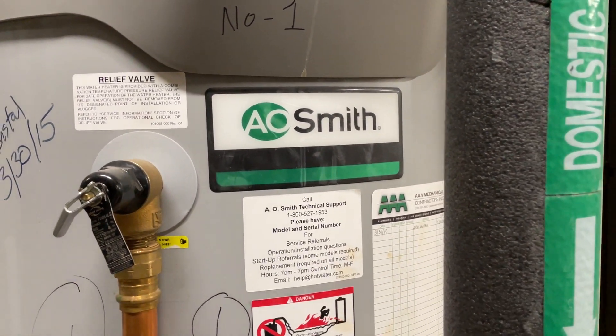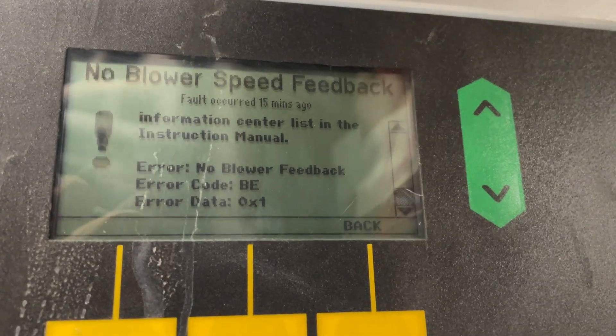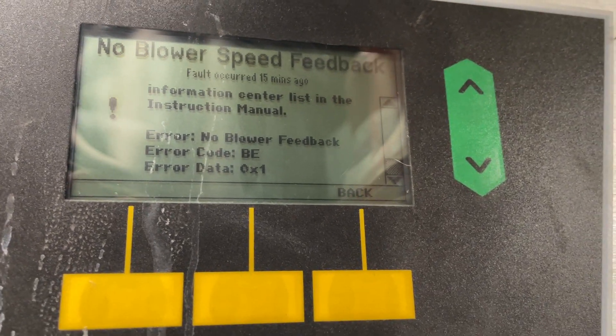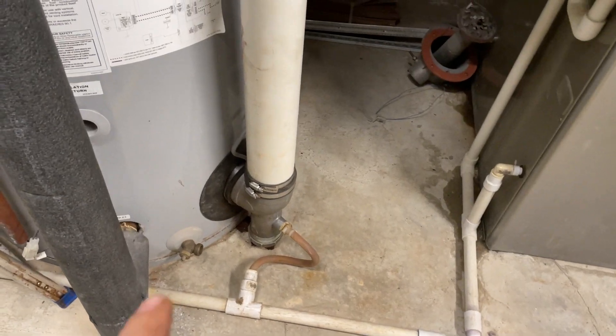This is an AOS water heater. It's saying no blower speed feedback error — error code BE, data 0x1. I opened this one and cleaned it; it was full of debris. After cleaning, it still keeps saying the same error.